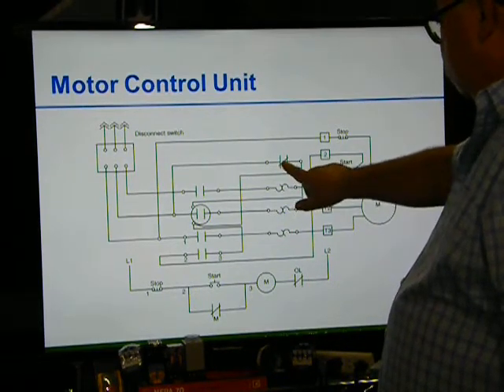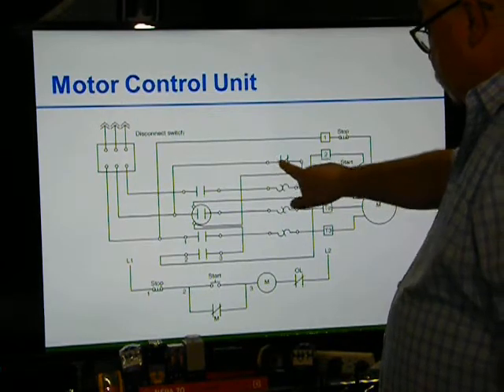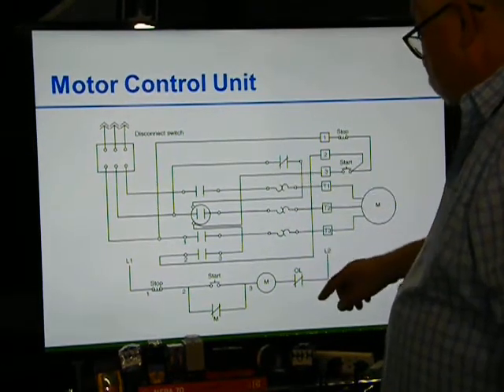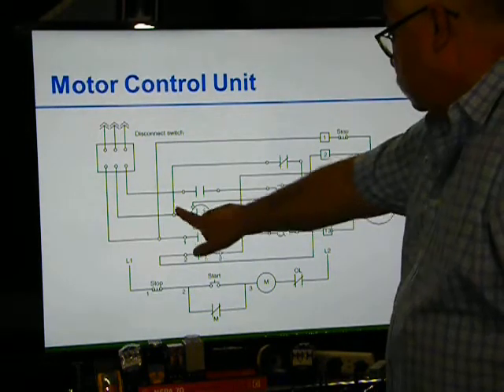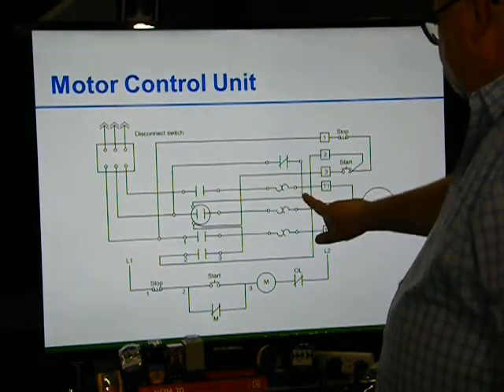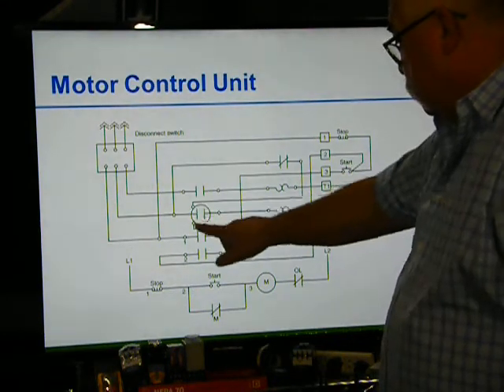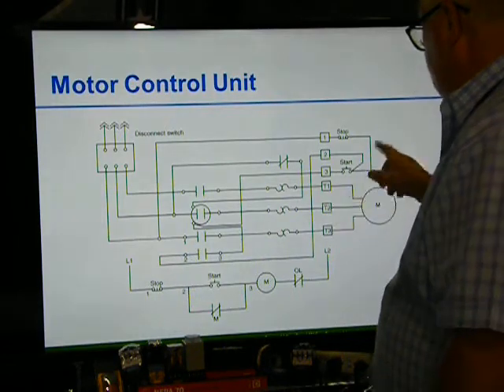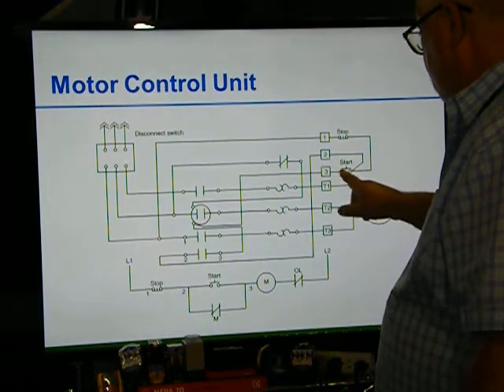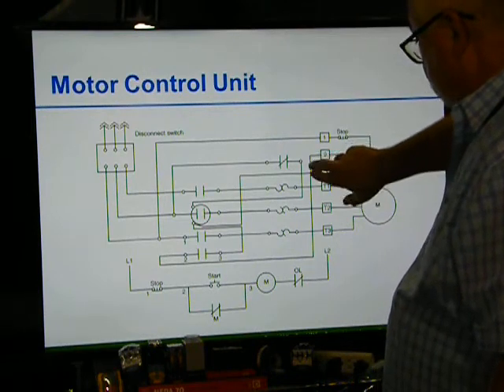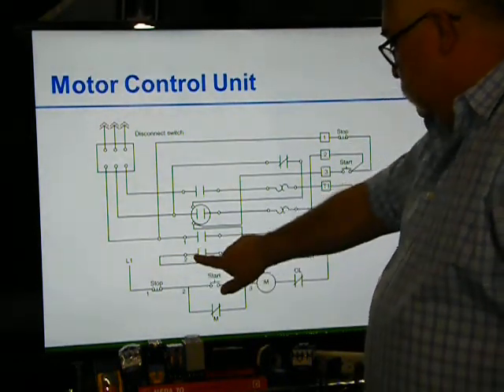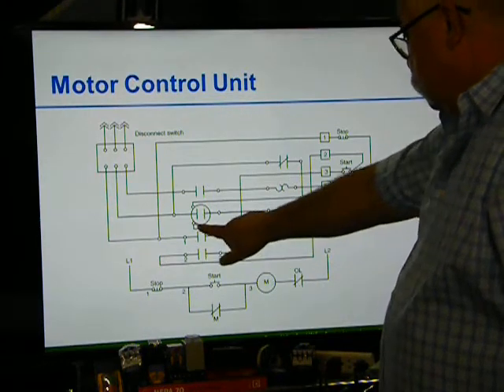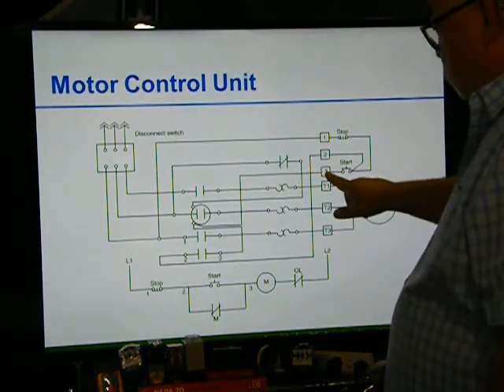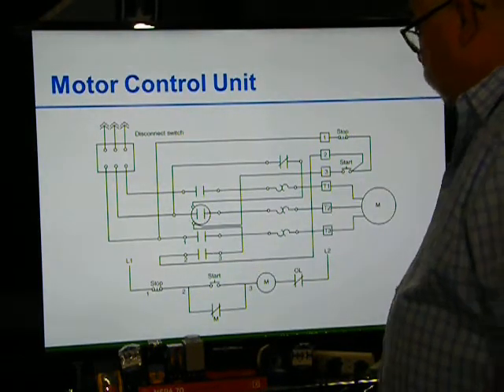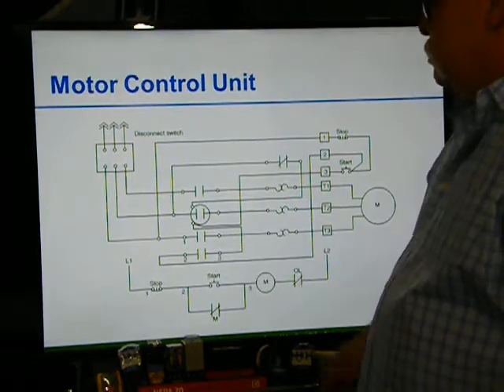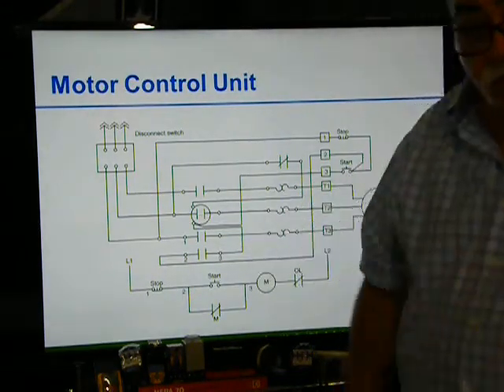And then here are my overloads, the other contact on my overloads that's normally closed. That comes off of number 2 right here and goes to the coil. The circle right here is the coil. Here's my other auxiliary, which comes off the start here and here. These 2 wires come in here. One comes this way to here, and the other goes to the coil. You can either have them here or in the coil, it really doesn't matter. This sees voltage going across, and it's going to stay energized and provide power to that coil.